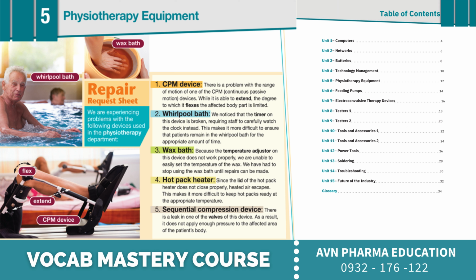4. Hot pack heater. Since the lid of the hot pack heater does not close properly, heated air escapes. This makes it more difficult to keep hot packs ready at the appropriate temperature. 5. Sequential compression device. There is a leak in one of the valves of this device. As a result, it does not apply enough pressure to the affected area of the patient's body.